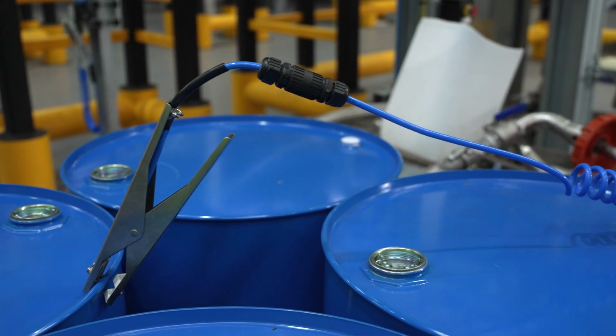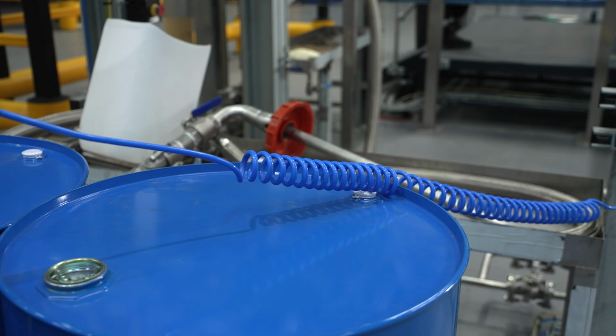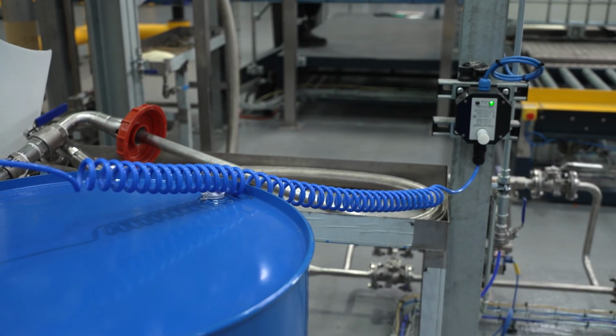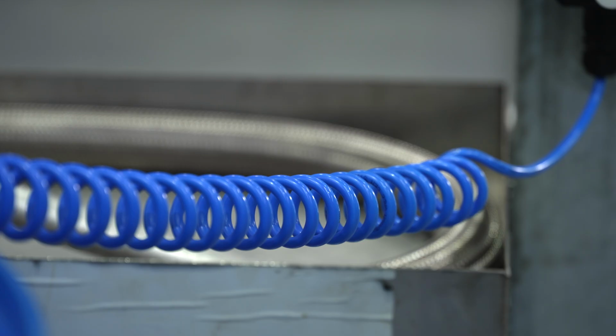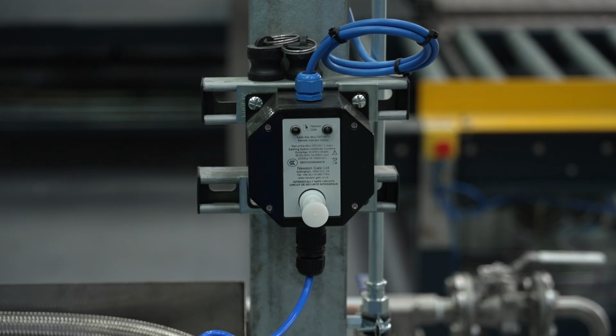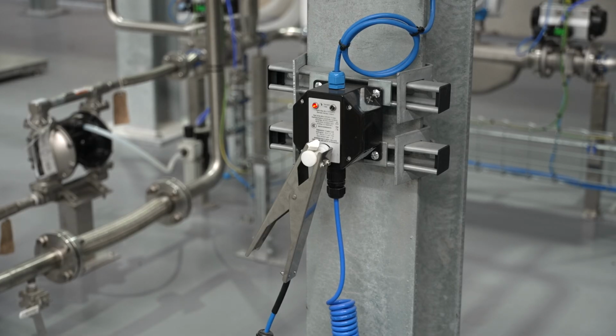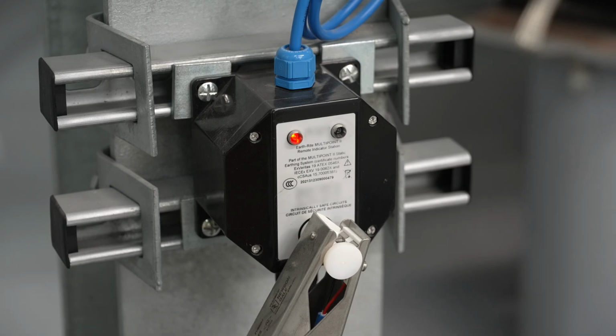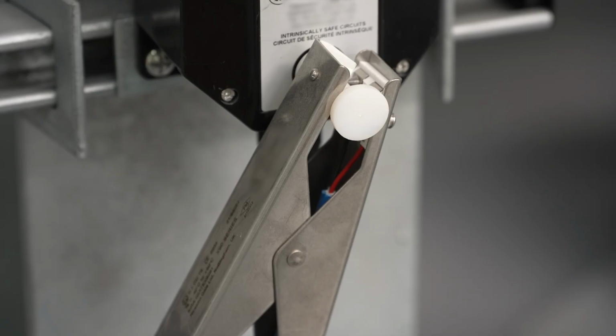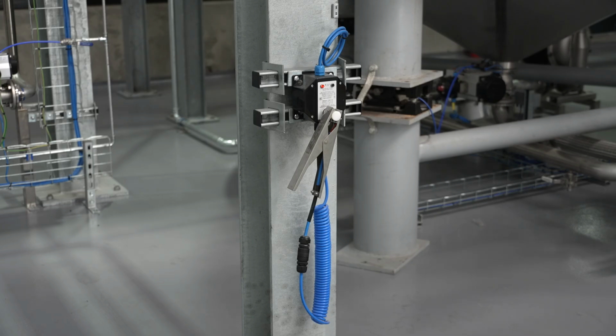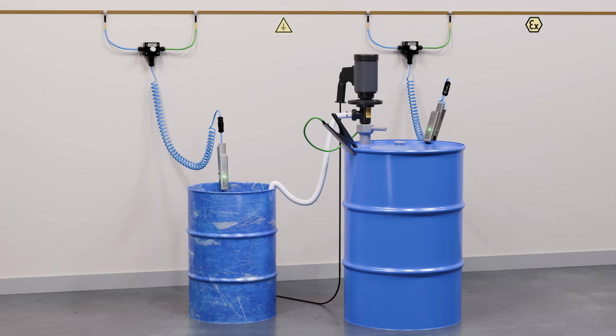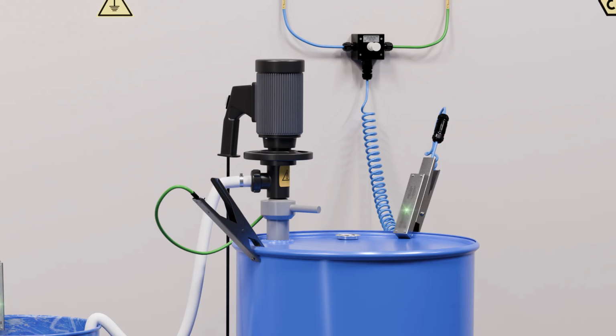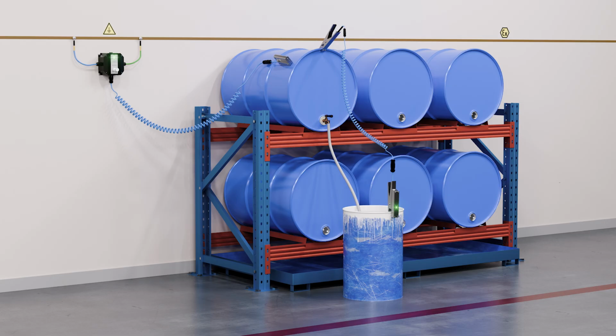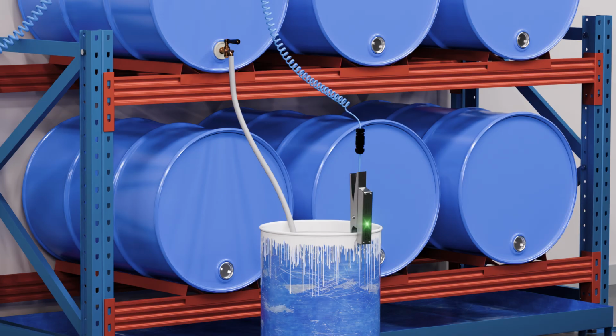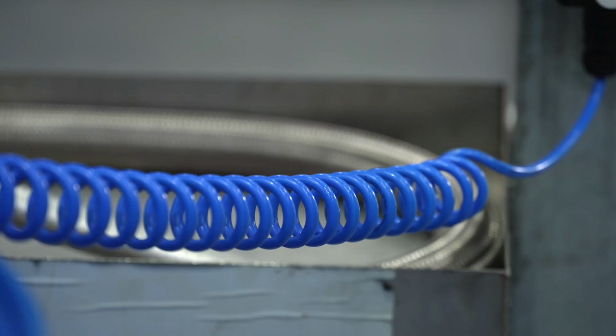Earthing establishes a continuous electrical path to earth and will remove charge rapidly. Conductive equipment is connected to an earthing electrode or to the building earthing system in order to prevent sparking. A bonding system connects conducting equipment together to maintain the same electrical potential. Electrostatic discharges cannot take place between objects that are at the same potential. All conductive objects electrically isolated from earth by insulators such as non-conducting pipes, connections, equipment supports or gaskets should be bonded and suitably earthed. Therefore, selection of the correct connections when transferring flammable liquids is very important.